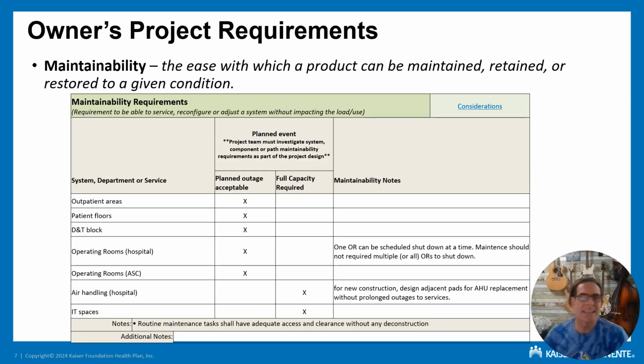Maintainability is the ease with which a product can be maintained, retained, or restored. For most spaces in Kaiser, this is a very important concept: a planned outage at partial capacity is acceptable. So when we need to perform maintenance on HVAC units or electrical systems or lighting in an outpatient area or a patient area, we plan a periodic interruption or reduction in service.